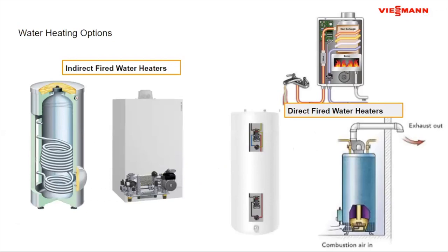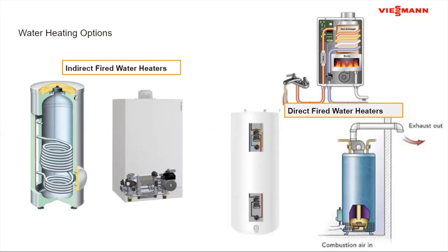Then the question becomes, all right, so how do I want to approach the water heating? Because there are a lot of methods. And in fact, these methods can be sliced and diced in a lot of different directions. I tend to look at it right off the gate as, is it indirect or is it direct heating? So direct fired are water heaters where the heat source is directly heating the water. So I have a flame here heating the water in this instantaneous water heater. Or here I have the flame heating the water directly in the storage tank water heater. And even with electric water heaters, I have electricity heating an electric element that directly heats the water. So these are direct methods.